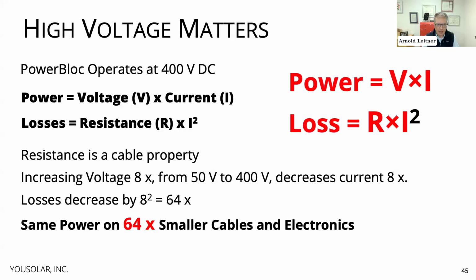The reason is simple. At 400 volts, the current drops down by a factor of 8 compared to a 50 volt system. Resistance is a property of the material, and loss is proportional to the current squared. So if I drop my current by a factor of 8 while delivering the same amount of power, since power is voltage times current and loss is resistance times current squared, I can decrease my losses 64 times by going to a higher voltage. Or reversed, I can run the same power over cables that are 64 times smaller, with commensurably smaller electronics than at 50 volts.